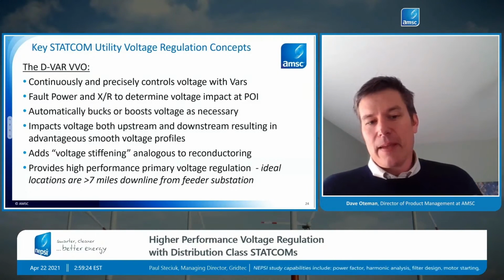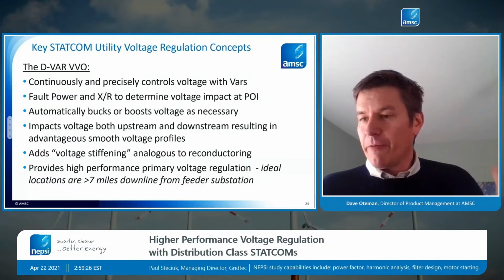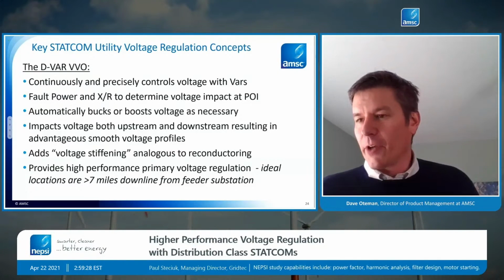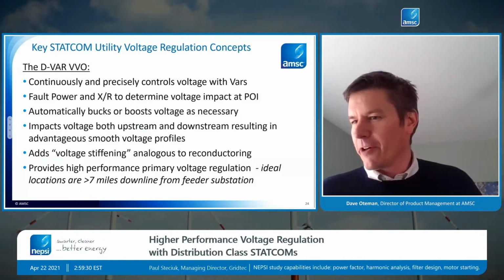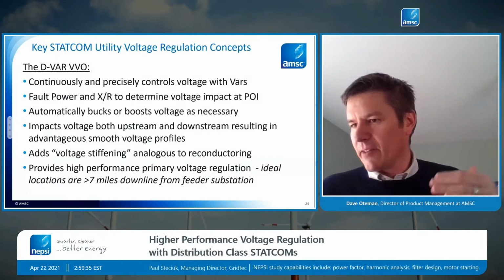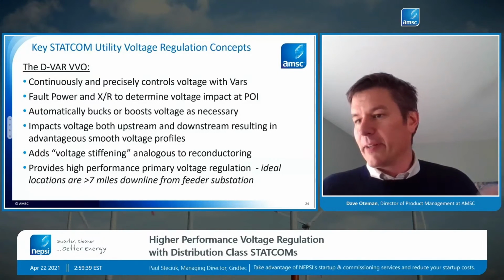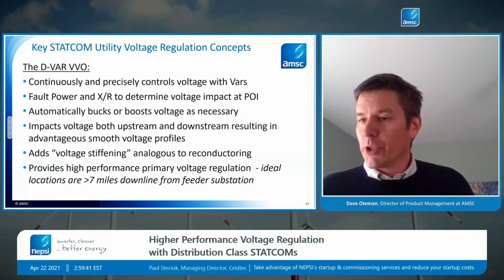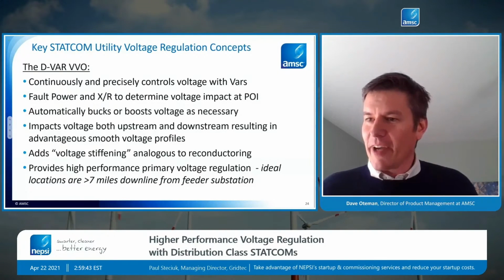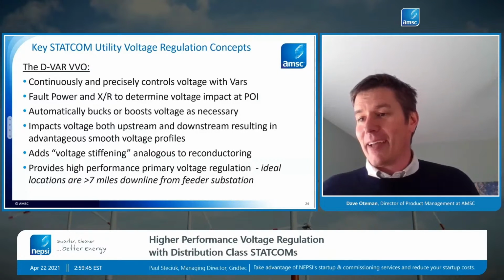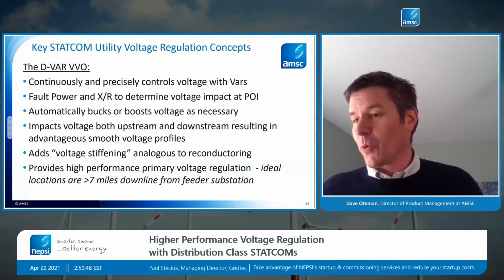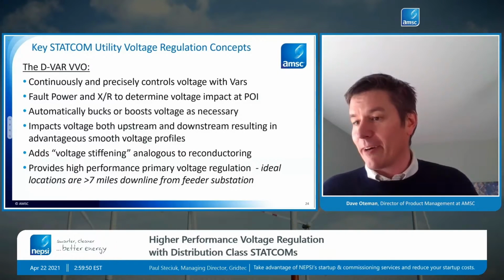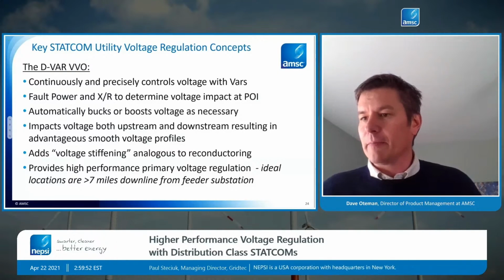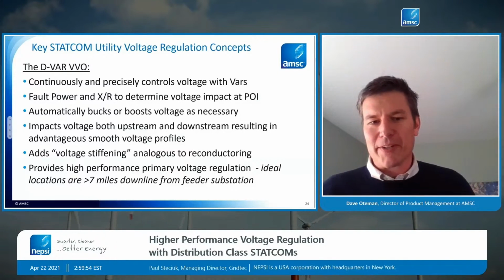And then lastly, this idea of, okay, where is it most effective? So basically 8 miles down line and further is where we see a lot of our installations. That's because it's starting to impact the voltage by about 4 or 5% or more, and with the hybrid, even more than that. So that's really where the STATCOM is most cost effective. And like I mentioned, that's a nice fit because that's where most of the power quality problems reside, around the end of that circuit on a distribution system.